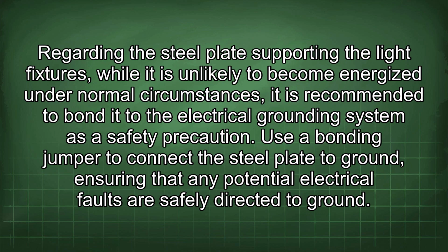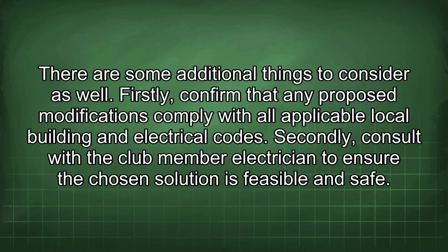Regarding the steel plate supporting the light fixtures, while it is unlikely to become energized under normal circumstances, it is recommended to bond it to the electrical grounding system as a safety precaution. Use a bonding jumper to connect the steel plate to ground, ensuring that any potential electrical faults are safely directed to ground. There are some additional things to consider as well.